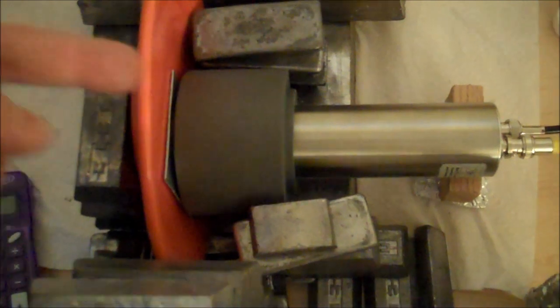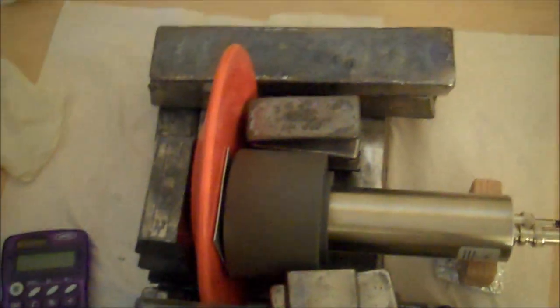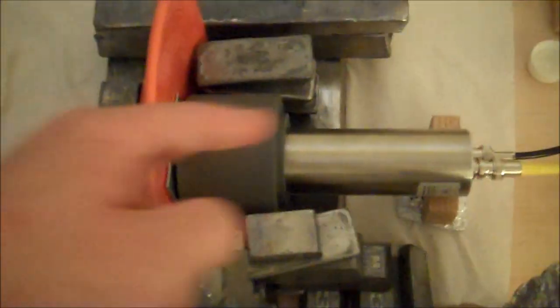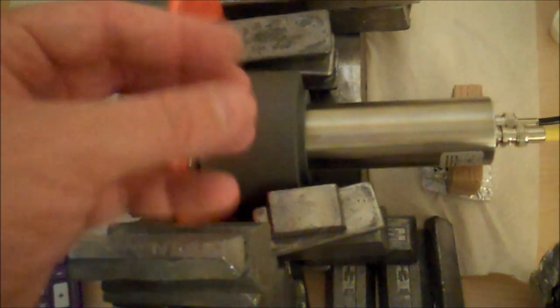The gamma rays are coming from here. They're hitting the detector crystal. The crystal is producing light. The amount of light is proportionate to the energy of the gamma. The light is then hitting a photocathode and producing a burst of electrons. The number of electrons is proportionate to the amount of light, which is proportionate to the gamma. The electrons go up this photomultiplier tube. There's 10 stages, gaining more and more energy, but still being proportionate to the energy of the gamma. Those then fly down the little tube here.